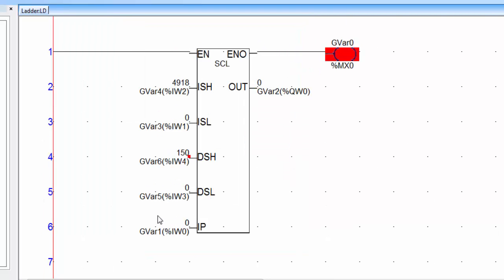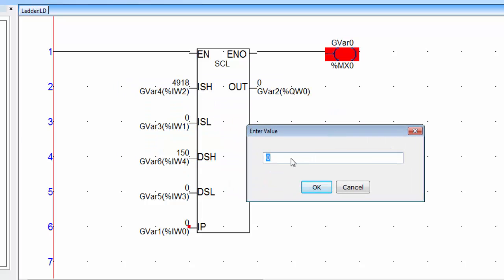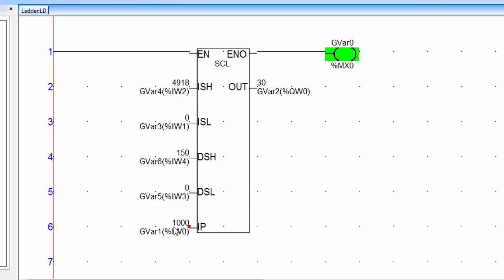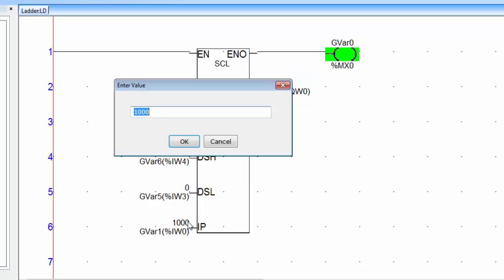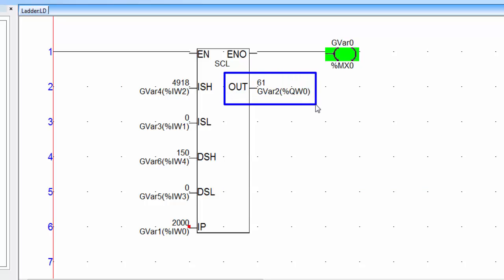Go for offline simulation. Initially the IP value is 0 since we are not using the analog channel — this is saved in G variable 1. Double click on IP and provide any value for the analog input. If I type 1000, the temperature is 30°C and you will get that value in the Out variable. If I type 2000, the temperature value is 61°C. You can go up to a maximum of 150°C with this scale instruction setting.